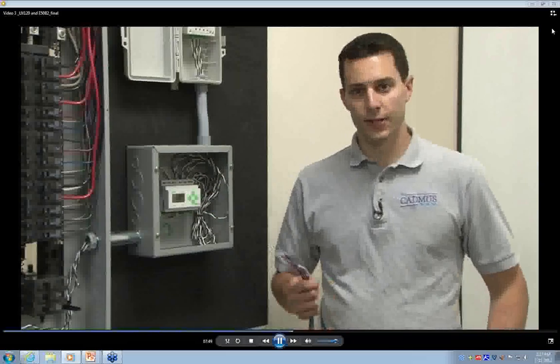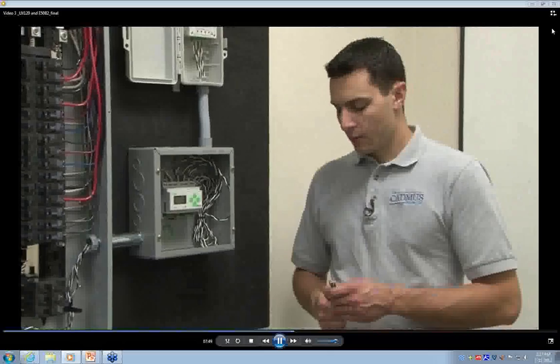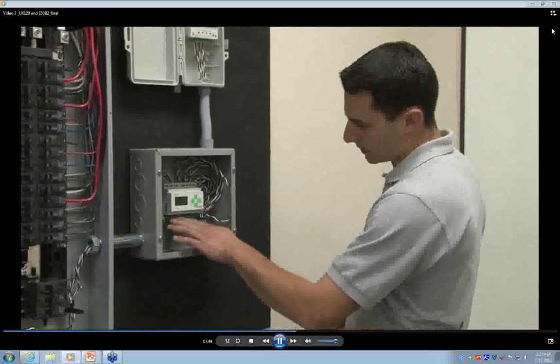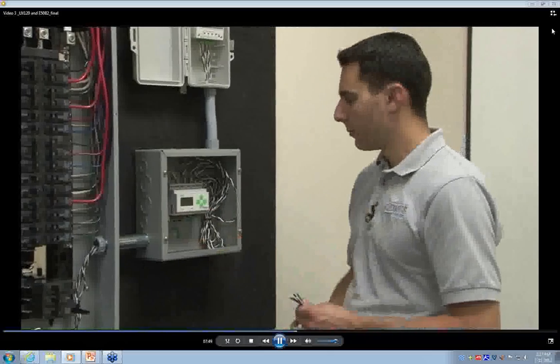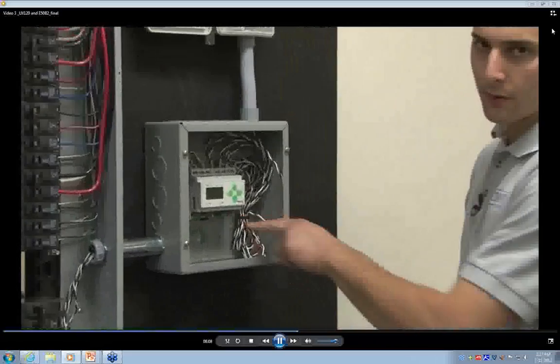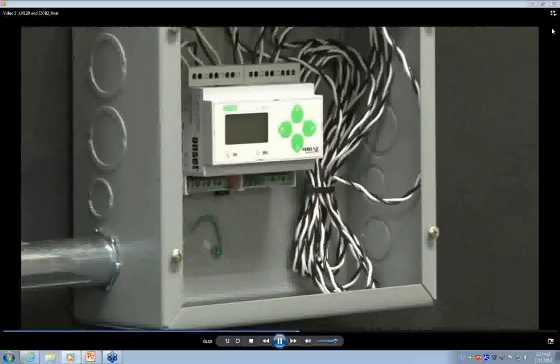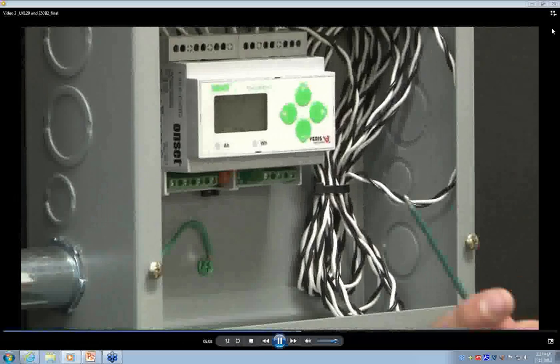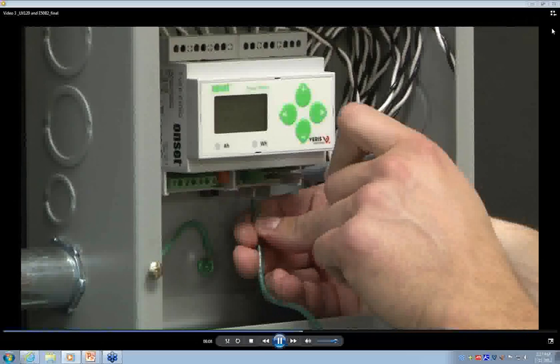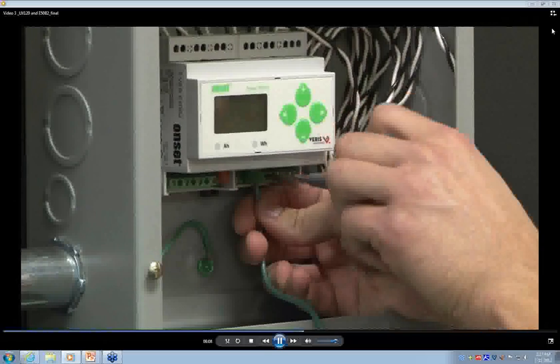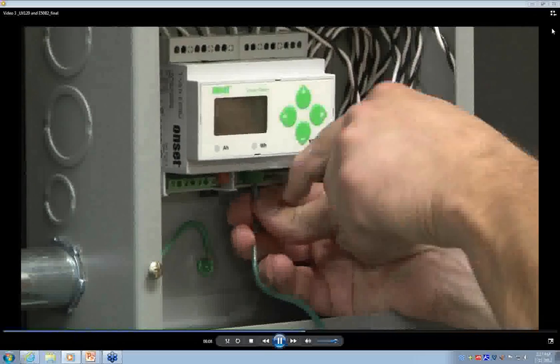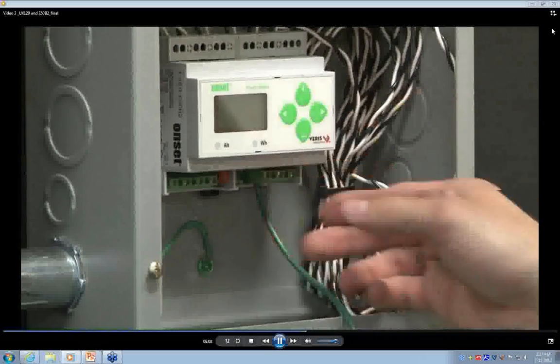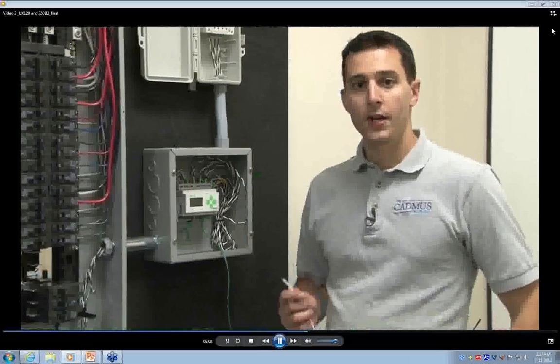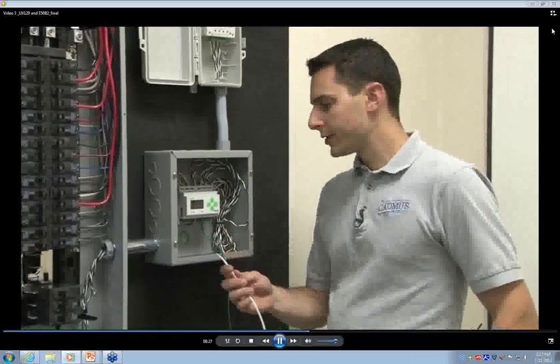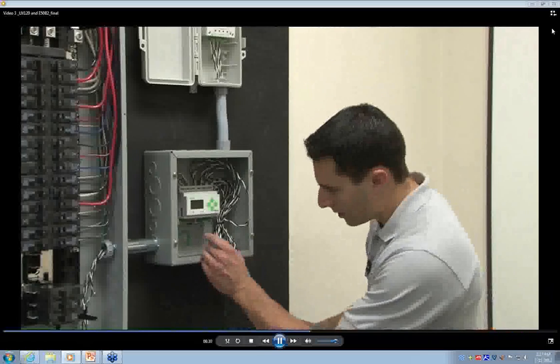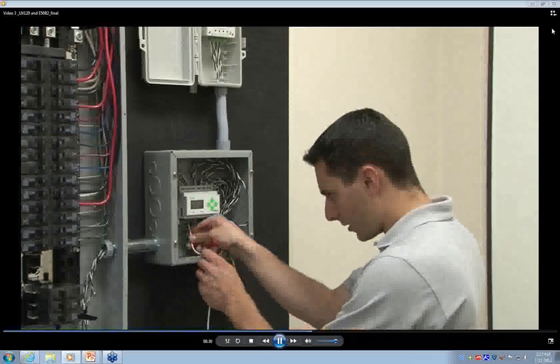We'll now install our voltage lead set on our power meter. We'll connect the phase conductors to the lower left-hand side, and we'll also connect conductors to the lower right-hand side to power the meter. We'll start with our green ground connection. This connects to the left-hand terminal of our control power block. Our next connection is our white neutral conductor. This will connect to the far right terminal of our voltage input terminal block.